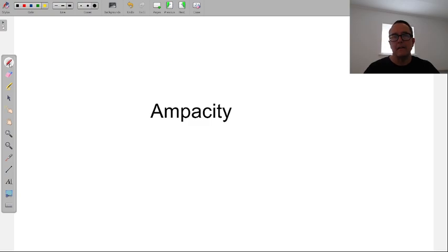Right? So I might say the ampacity of the receptacle. That's a little bit incorrectly used, but I know what I'm saying. I'm saying the receptacle has an ability to hold 15 amps, and if I plug in a load that has 12 or 15 amps, we're all good there. Higher amperages will then damage the receptacle. But ampacity is more a word centered around conductors.